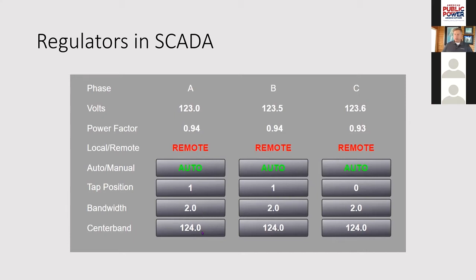Then we can lower this voltage. This center band voltage is how we would manipulate the voltage lowering from OATI. We'd send new commands to progressively lower the voltage until we got feedback from the field. So that's the interaction between OATI and the SCADA system and our substations.